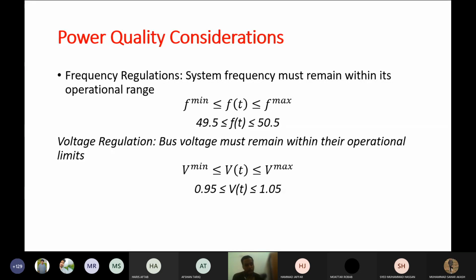However, in distribution networks such as the 220 volt network installed near our homes, we have a 10% operational constraint. That means in a 220 volt system, the voltage should not be more than 240 volts and should not be less than 200 volts. This is the voltage flexibility for distribution networks.